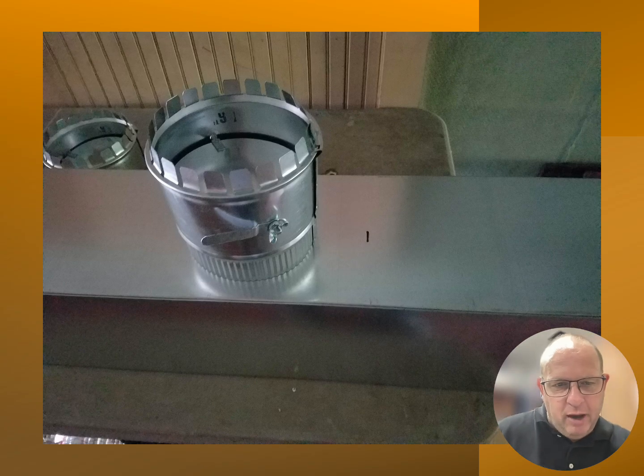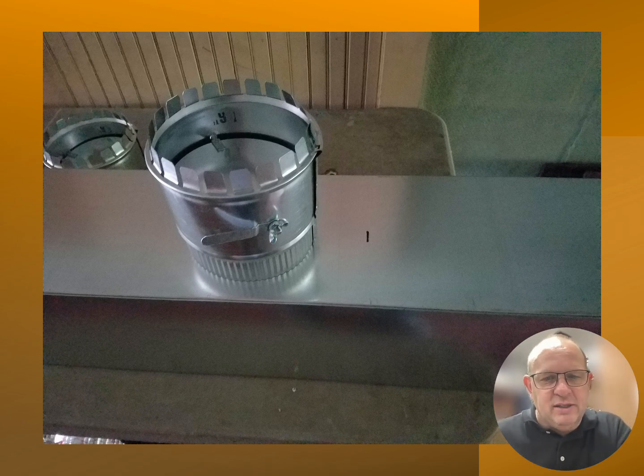Okay, so what we're going to do now is we're going to go through the actual process of installing a branch run on the main trunk line that's running for the air conditioning or the furnace or any air distribution system that we can see. We got a couple of different parts that we are looking at when it comes to this. We are going to install a damper on the takeoff of this system.